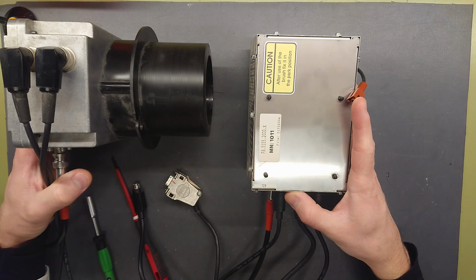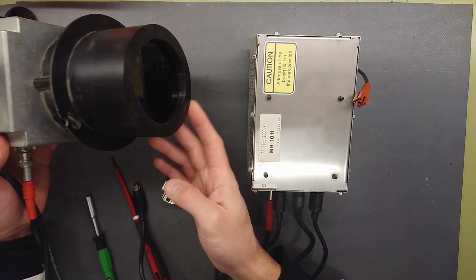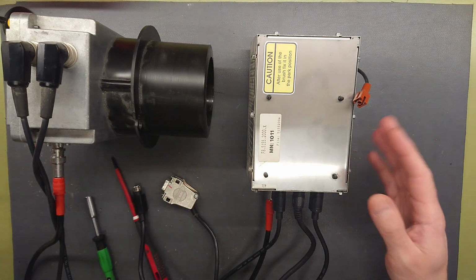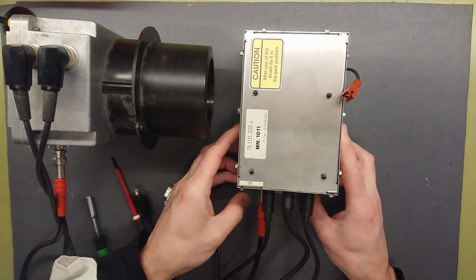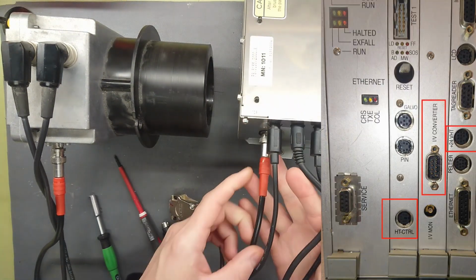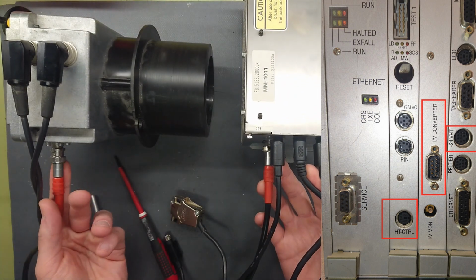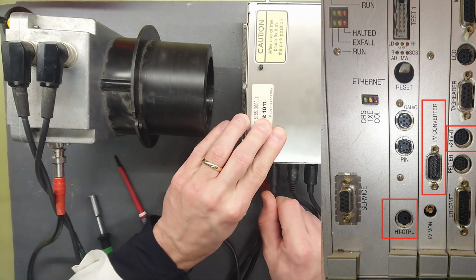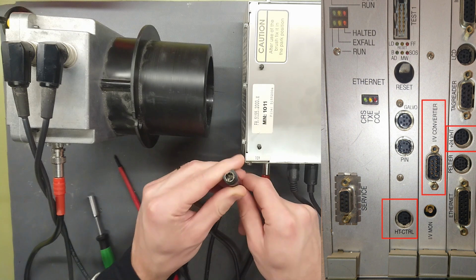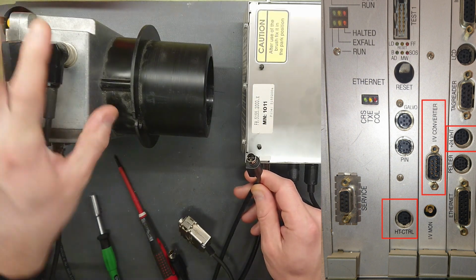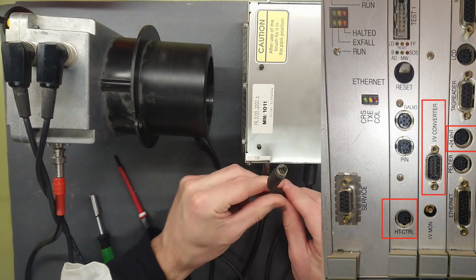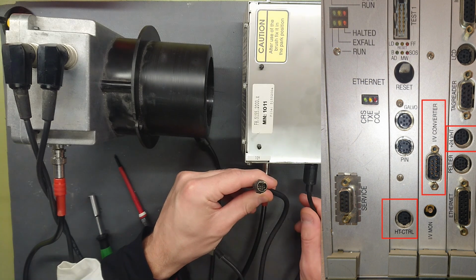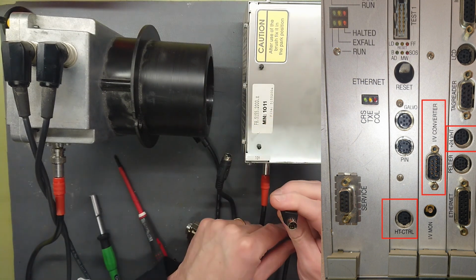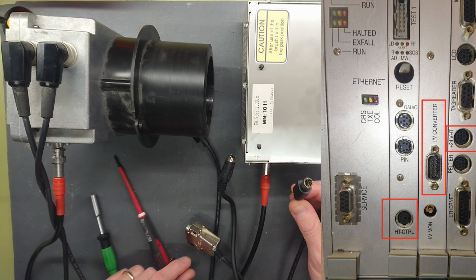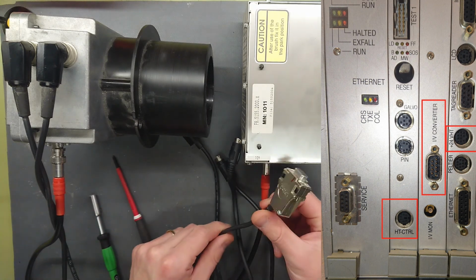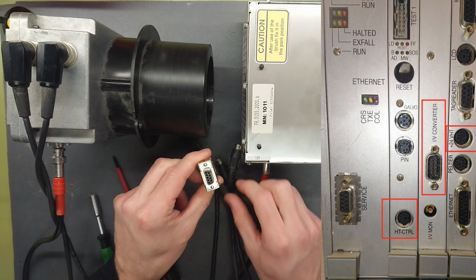We have the high voltage power supply, and we have the photomultiplier tube itself. Now, this was all connected up to the computer. So if we just bring that front up, we can see that we have 4 connectors here at the front. One is the red high voltage power supply over to the PMT itself. Then we have the first connector here, just 3 pins. That also goes over here to the PMT assembly. The next here is a 24 volt plug. As we can see, that corresponds to the front of the computer. And we have a 6-pin plug here, which is the high tension control. And then we have the 9-pin connector here, which is the serial connector or IV converter.